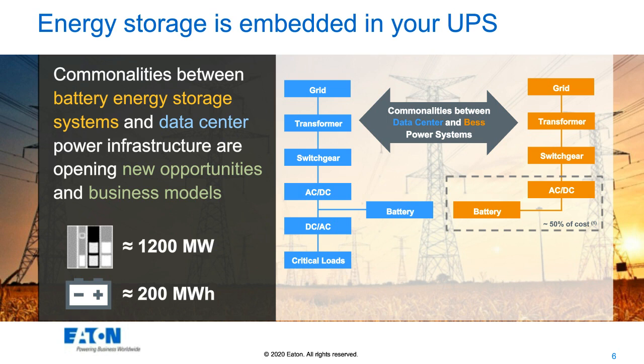you see the blue block diagram of a traditional UPS system consists of the parts that we would expect. I've got a connection to the grid. I've got a step-down transformer and switchgear. I've got a rectifier that converts AC to DC and charges up the battery. And the inverter takes DC power from the battery or the rectifier and basically converts it to AC and sends it out to the critical loads in the data center. And that's traditional UPS operation.